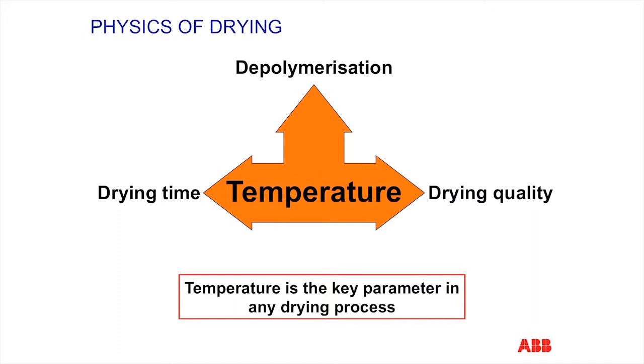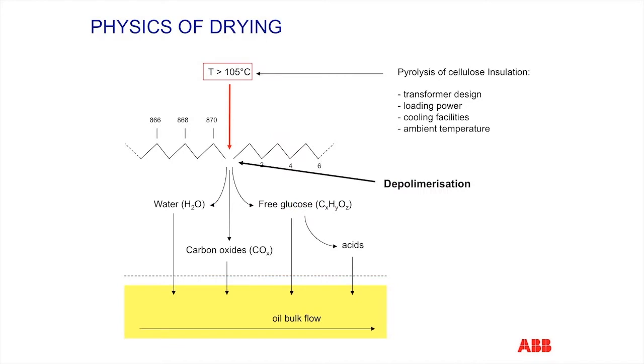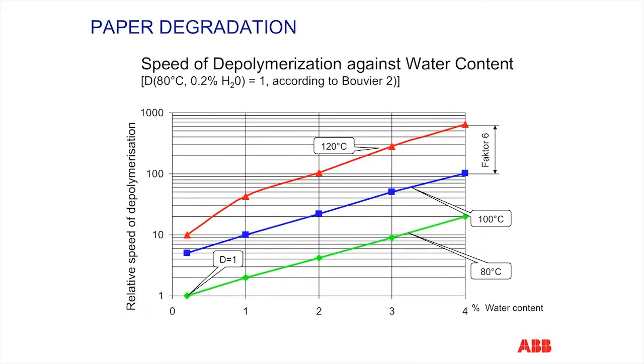Low-frequency heating concept. After working through the physics of drying, one is left with the fact that temperature is the key parameter to control. Too high a temperature can destroy the transformer. Too low a temperature, and the efficiency and effectiveness become so slow as to be useless. The heating strategy needs to be able to implement a number of constraints to be effective and practical. As this process is frequently a mobile one, there are more constraints to provide the effective heating required to reach the needed drying temperature.